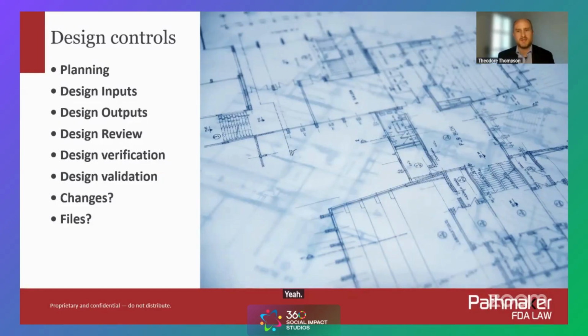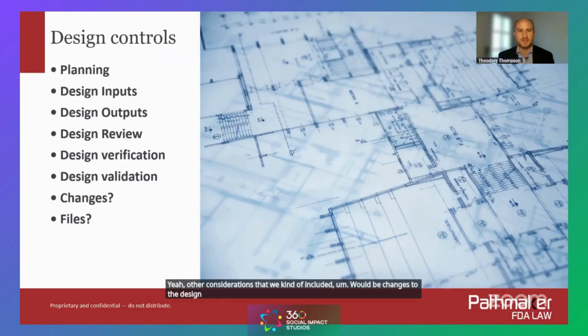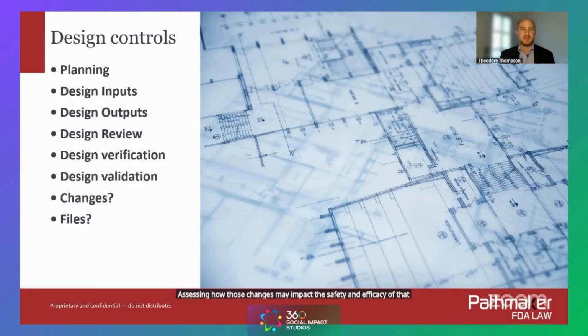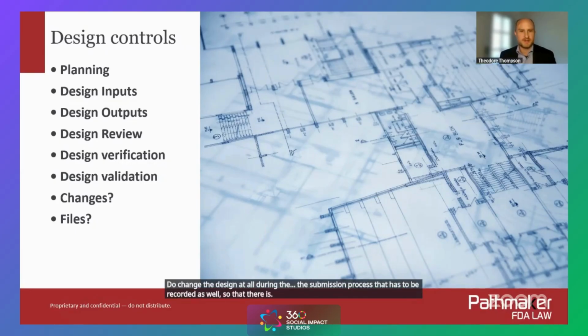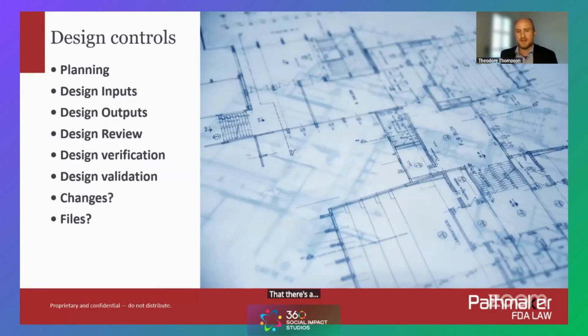Other considerations that we included would be changes to the design, and how that's recorded. That falls under the heading of design controls and those different files that you need to keep to show that you've gone through the required steps in assessing how those changes may impact the safety and efficacy of that product. That applies both before you submit to the FDA and after, so all of those steps can be traced. It applies most often after the FDA submission, but if you do change the design during the submission process, then it has to be recorded as well, so that there's a record of it to support the safety and efficacy of the device that you're putting on the market.